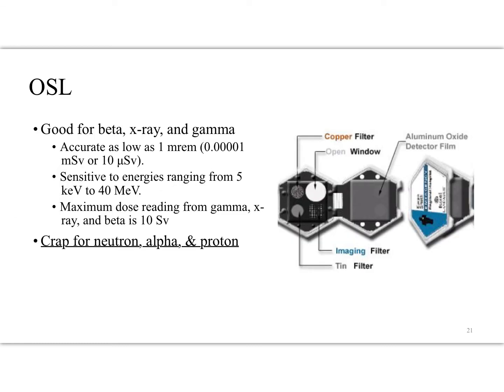The OSL is our favorite — we use it a lot in departments because it's affordable and easy to read out. It has a crystal of aluminum oxide inside the detector, along with an open window, a copper filter, and a tin filter, which give different depths to which the radiation dose may have been received. The open window tells us a tissue skin dose, the copper filter tells us a deep tissue dose, and the tin filter tells us the lens of the eyes dose. The radiation interacts with the aluminum oxide, changes the crystal structure; then when it's read out, it's scanned with a laser and gives off optical light in response, which is then measured and plotted on a glow curve to give a range of what type of exposure the individual may have received. We can also estimate half value layer using the tin and copper filter comparisons — that's on textbook page 730.